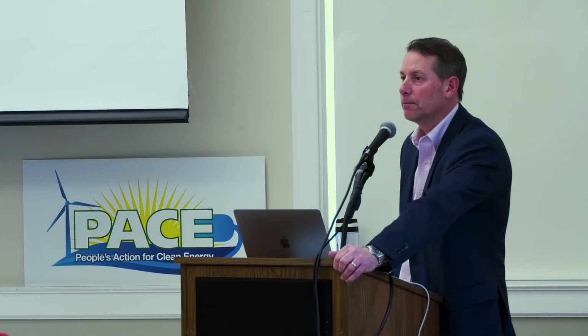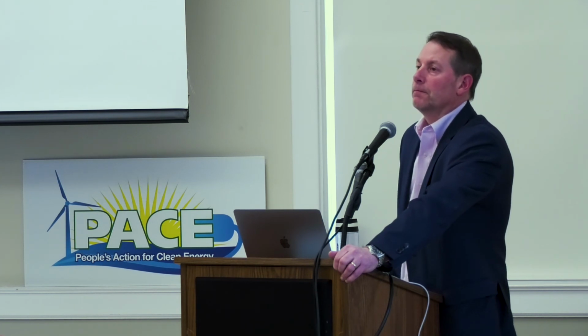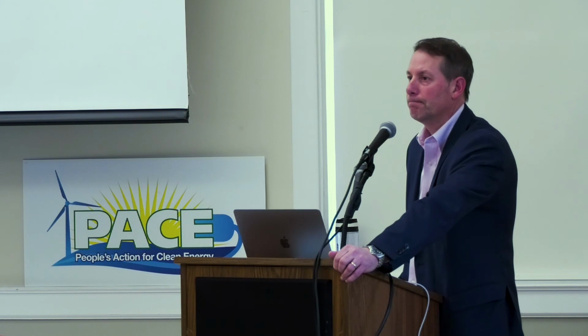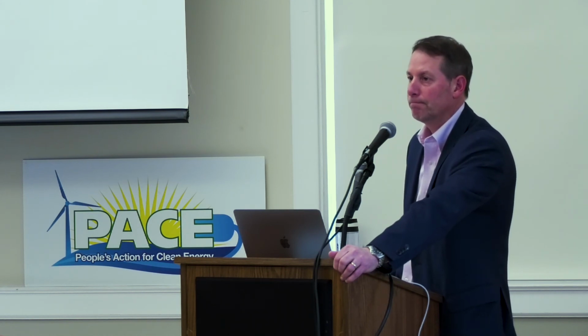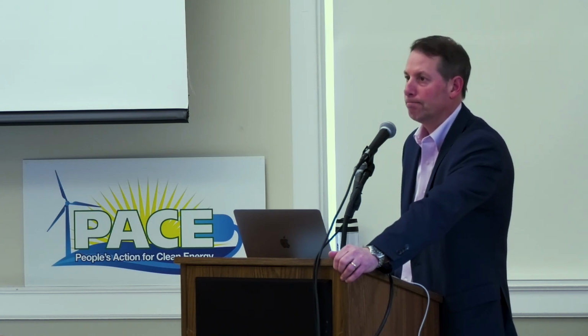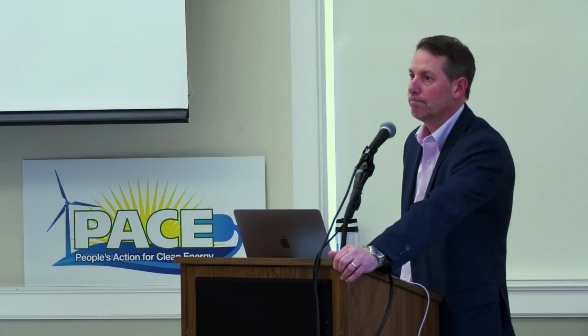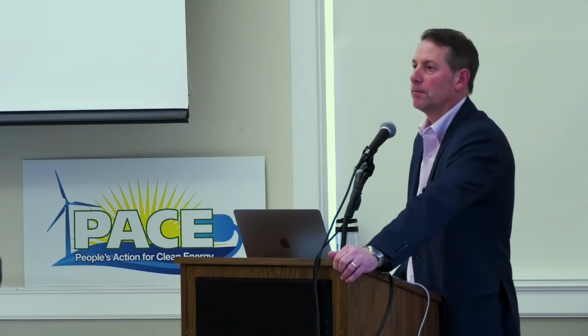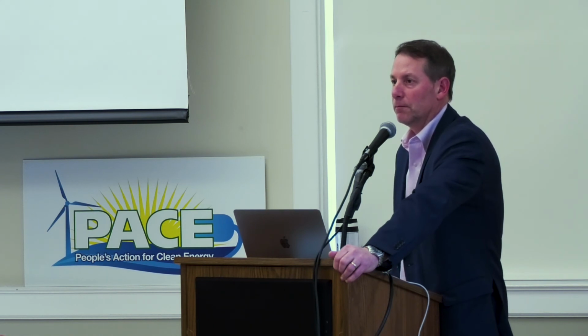Schools are a peculiar occupancy, say, compared to almost anything else like an office building, because they have large common spaces that aren't used all the time. I'm thinking of auditoriums, cafeterias, gymnasiums, maybe a library. So let's say a school has 500 students in it, and they're in their classrooms. You'd want to supply that ventilation to the classroom. Sure. But you wouldn't want to supply it to the unoccupied rooms. And so it's really important that you use smart controls to control the ventilation, because it is always expensive to use. So you often connect with the lights, and the lights are on a motion sensor, so when they shut off, the ventilation also shuts off in that space.